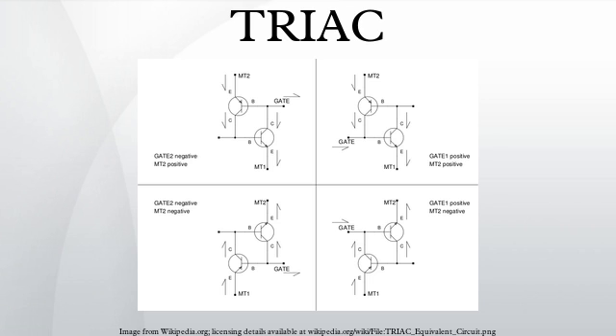For higher powered, more demanding loads, two SCRs in inverse parallel may be used instead of one TRIAC. Because each SCR will have an entire half-cycle of reverse polarity voltage applied to it, turn-off of the SCRs is assured, no matter what the character of the load. However, due to the separate gates, proper triggering of the SCRs is more complex than triggering a TRIAC. In addition to commutation, a TRIAC may also not turn on reliably with non-resistive loads if the phase shift of the current prevents achieving holding current at trigger time. To overcome that, pulse trains may be used to repeatedly try to trigger the TRIAC until it finally turns on. The advantage is that the gate current does not need to be maintained throughout the entire conduction angle, which can be beneficial when there is only limited drive capability available.